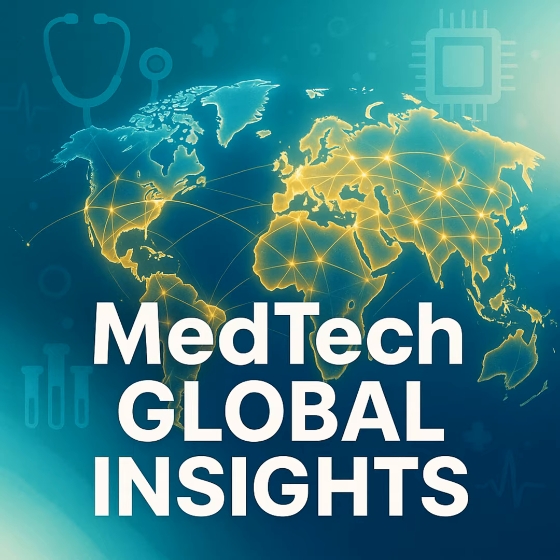This is not simply a list of competitor products. It is a comprehensive analysis of the specific clinical condition your device addresses. For example, if you are marketing a new absorbable suture, your state-of-the-art analysis must thoroughly evaluate all current treatment options for wound closure, including different types of sutures, staples, and adhesives. It needs to discuss the respective clinical benefits, risks, and limitations, establishing the current clinical benchmark that your device will be measured against. A superficial review here is a red flag for any reviewer.